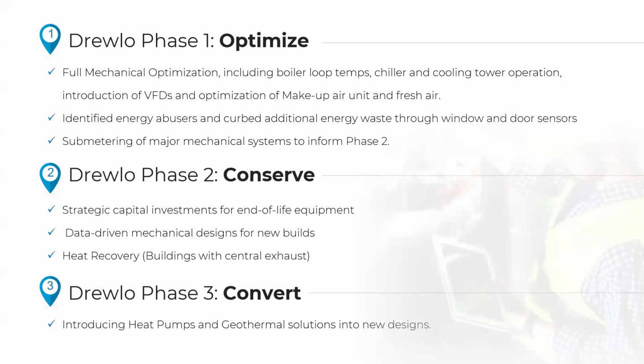Most rules of thumb for sizing mechanical systems in buildings—from the plant, the boilers, the chillers, to the pumps, the risers, all the way into the fan coils in the suites—in the case of a multi-res building, are typically too large. That's a holdover from when liability from a design perspective had to be the number one consideration, but we're no longer in those days. There has to be a line between liability and efficiency, both in terms of energy efficiency and energy costs. The best way to get engineers on board with downsizing mechanical systems in new buildings is to show real data, and we're actually having a lot of success with that.